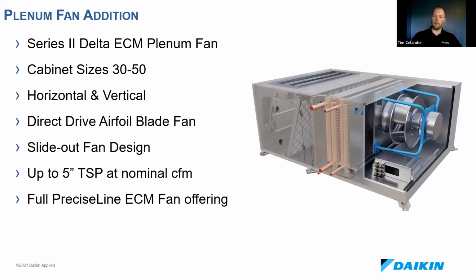It is an ECM fan, so you're going to be slightly more efficient than the VFDs. In addition to that, in the crazy supply chain world we've been seeing, you now have an option, if VFDs are driving extended lead times, to convert to an ECM motor, cut out the VFD, and try to hold lead times as well as we reasonably can.